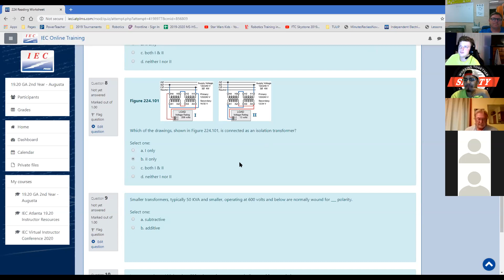Smaller transformers, typically 50 kVA or smaller, operating at 600 volts and below, are normally wound for additive. Larger capacity or higher than 600 volt transformers are typically wound for subtractive, going a lower amount.